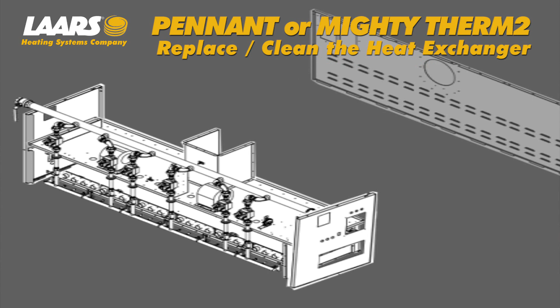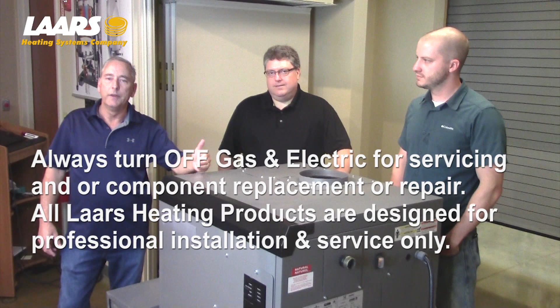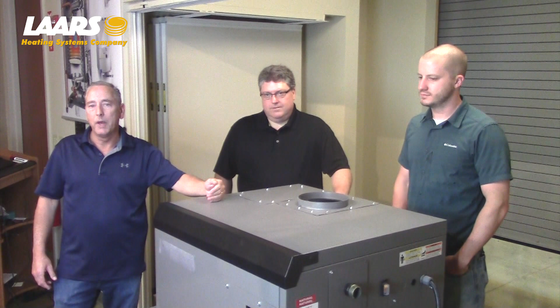This video is to show how to remove the heat exchangers for either cleaning or replacement on a Pennant or Mighty Therm2 boiler. For starters, we're going to remove gas and electric to the boiler, and then we're going to remove the jackets on the heat exchangers. The boiler we currently have in front of us is a small Pennant 500. This can also be done on the Mighty Therm2.